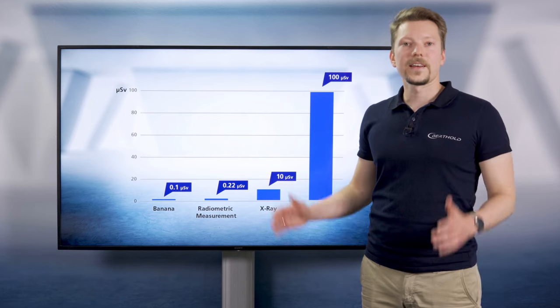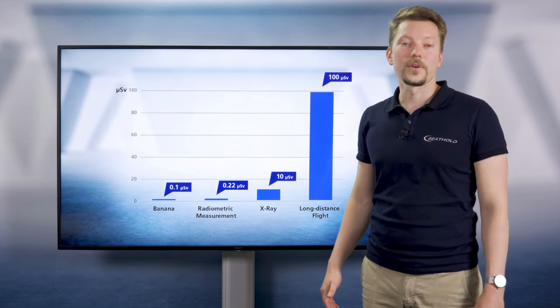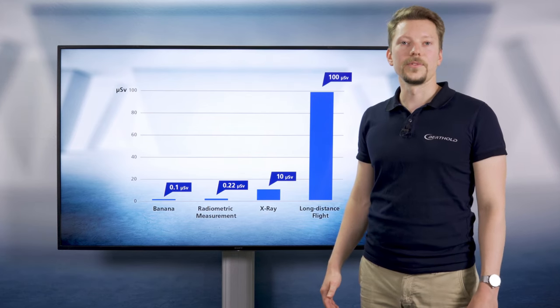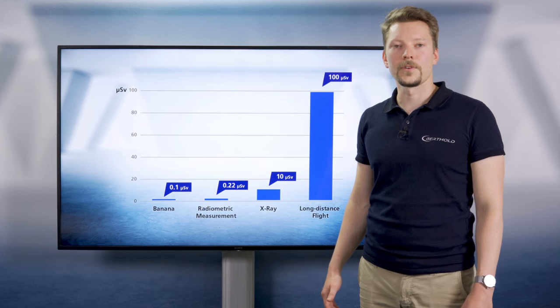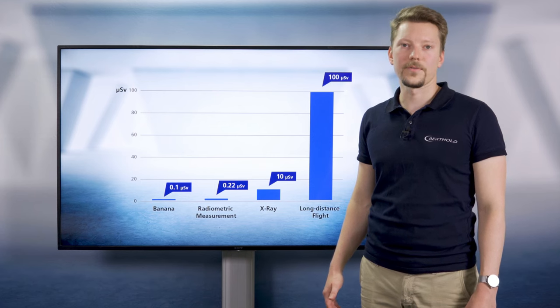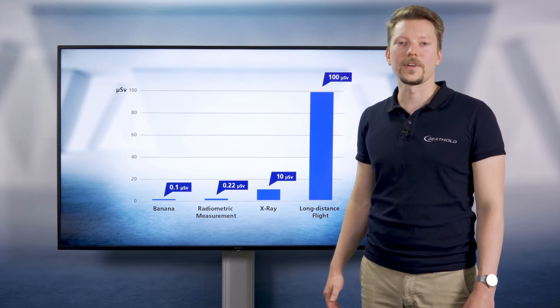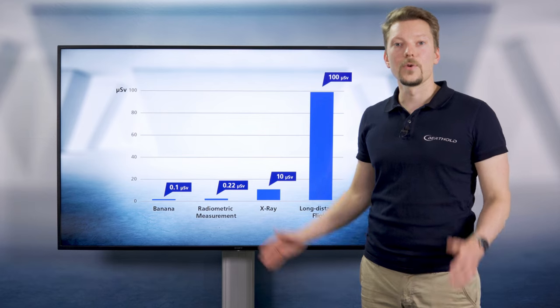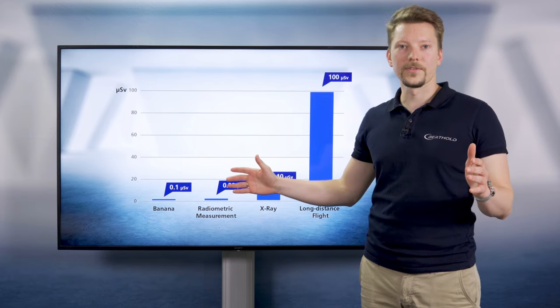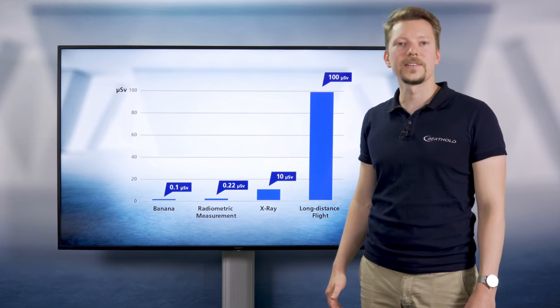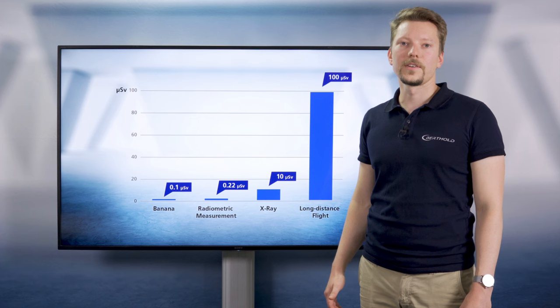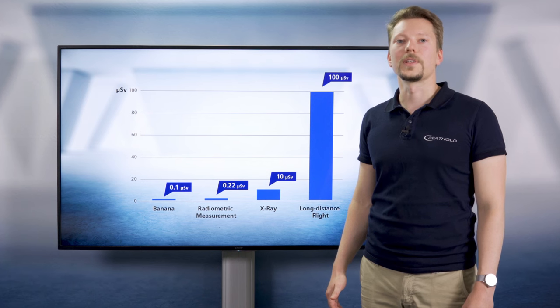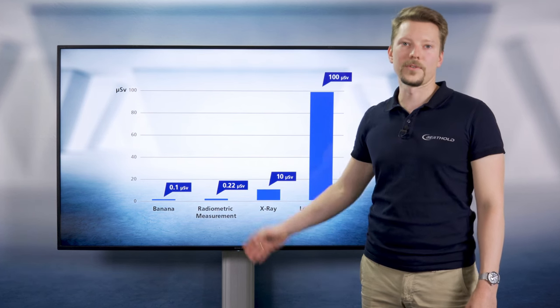Standing next to a standard radiometric measurement for density using the radionuclide cesium-137 and an activity of 3,700 megabecquerel in one meter distance for one hour, for example when maintaining the shield, results in a dose of approximately 0.22 microsievert.